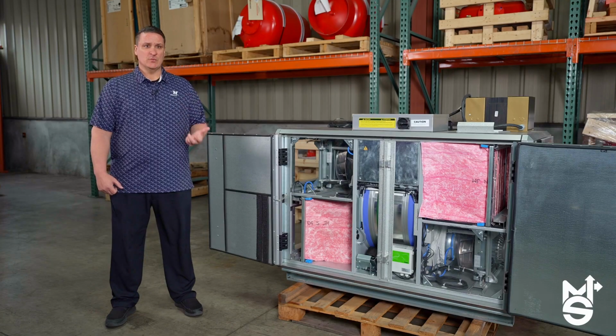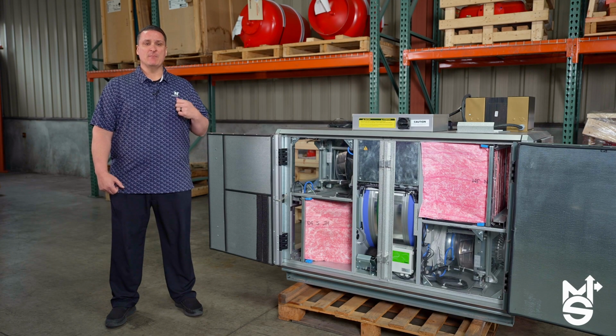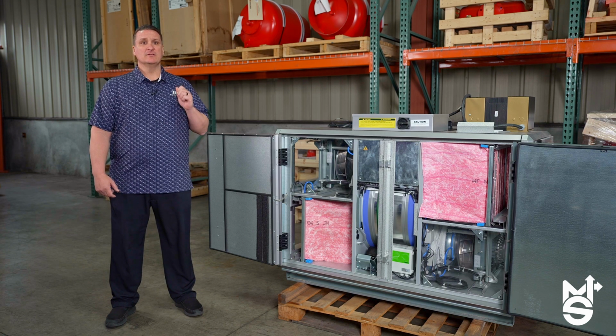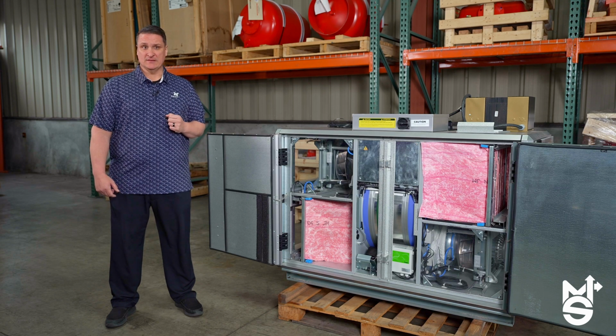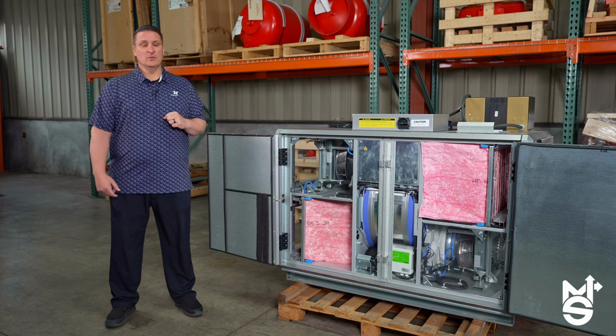Let's talk about Swegon's defrost control solutions. Swegon standardizes their controls by measuring the pressure drop across the rotary heat exchanger in real time. Swegon only begins the defrost cycle when pressure begins to build across these sensors, meaning that ice is beginning to form. Upon that, we'll begin a defrost cycle, but otherwise, we will not defrost, which maximizes the energy savings. Typical conditions allow Swegon to fully function without defrost down to minus 5 degrees Fahrenheit when using total energy wheels.